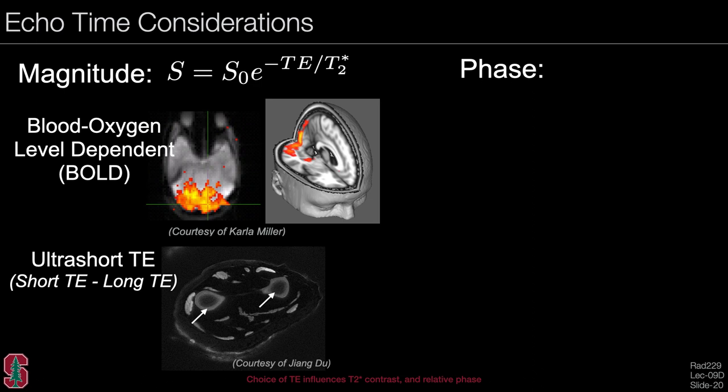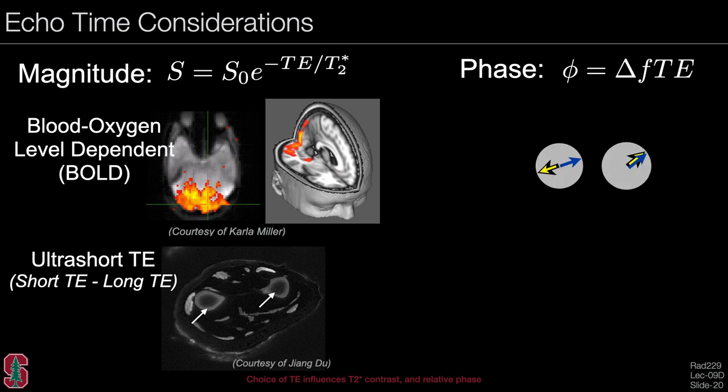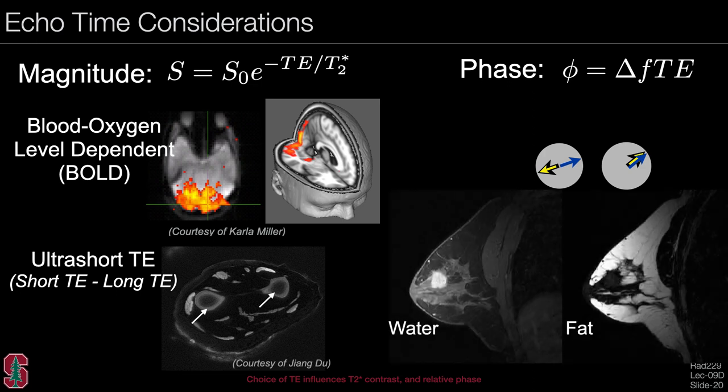Looking at phase considerations of echo time: the phase is the frequency variation times the echo time. A very common use of this is for fat-water imaging, where we acquire in-phase and out-of-phase images, which can be used to separate out the water component and the fat component in images.